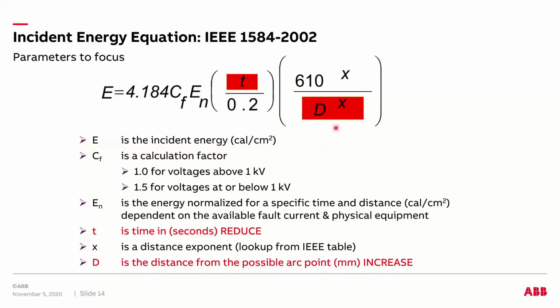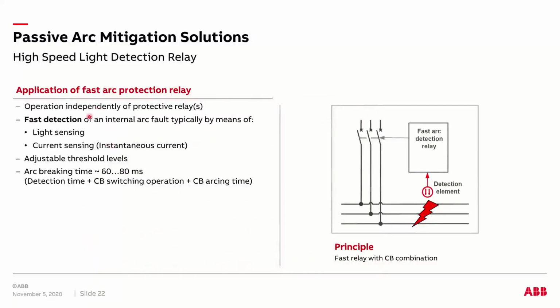the remote racking device, where we plug in that remote racking device, and then we bring the operator like 20 feet, 15, 20 feet away from the equipment. So by increasing the distance, the operator is not exposed to a higher incident energy level, right? And the other parameter that we can play with is time, right? So if we can reduce the time significantly, we can directly, proportionally reduce the incident energy level that is being generated in front of the equipment, as well as within the equipment.